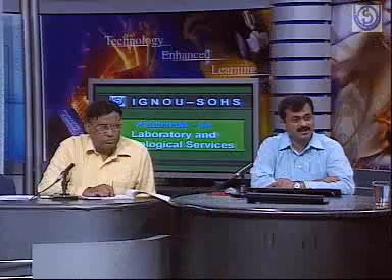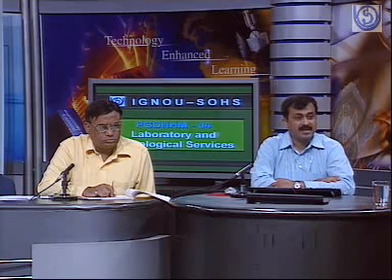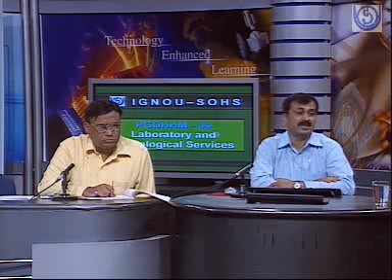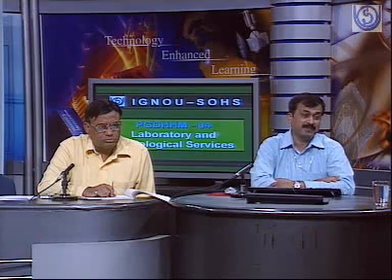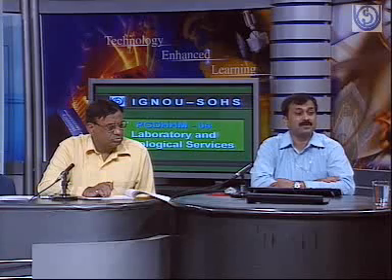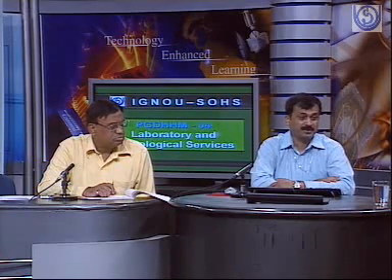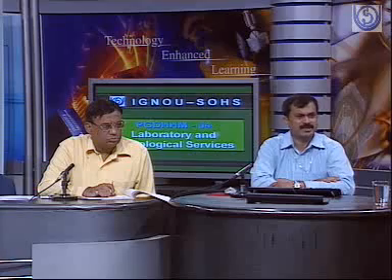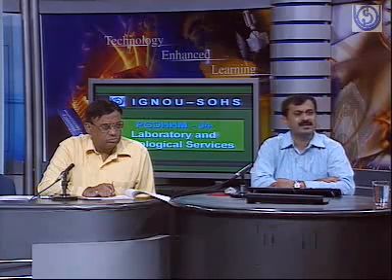So in this country there are various other requirements also, but this is a primary requirement for all radiological installations, whether that is CT, MRI, X-rays, mammography, even cardiac cath lab. Generally people forget about the cardiac cath lab. That is also a very important area where a lot of radiation is generated, and people tend to forget to take a clearance from the AERB for this purpose. Nowadays it has become mandatory. In fact, the machines themselves have to be passed by them, then the design has to be passed. Then only they are installed. Okay, sir. Thank you, sir.